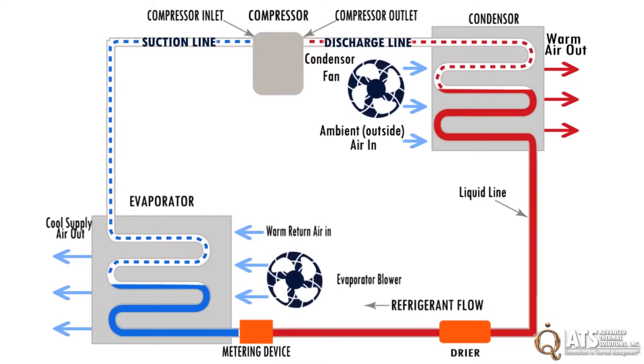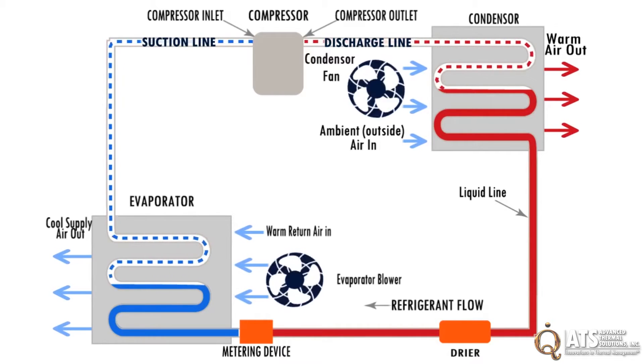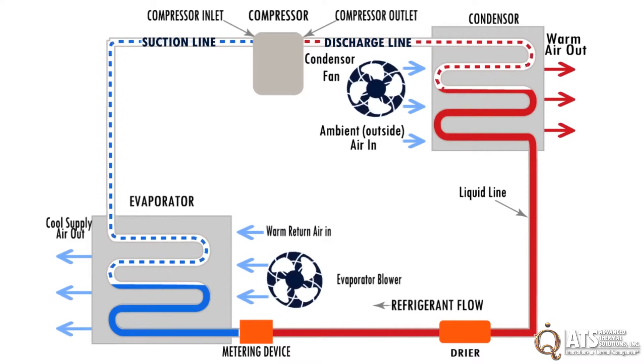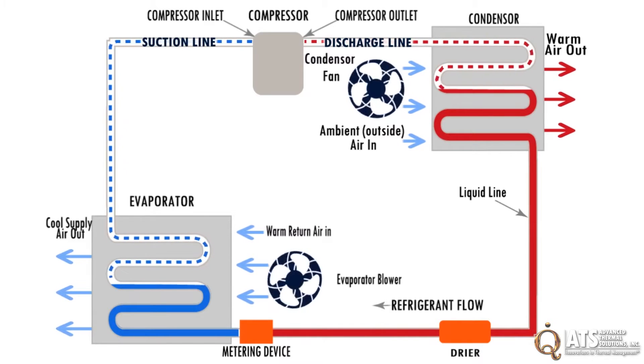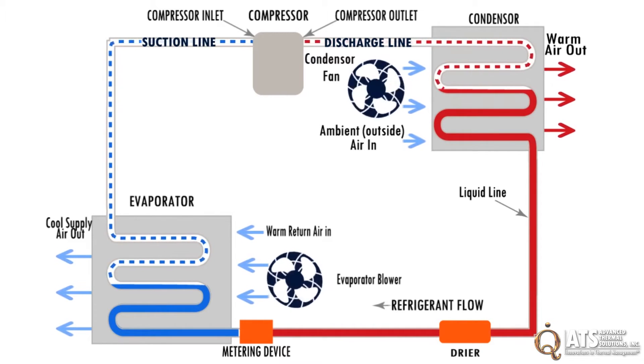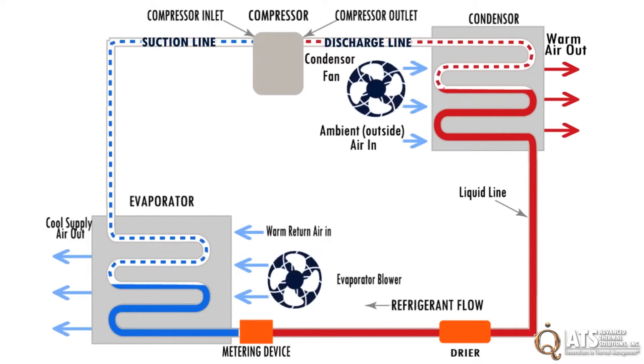The ATS recirculation chiller's refrigeration cycle shows red dashes where elevated-temperature, high-pressure refrigerant gas flows. Solid red shows the chiller's warm high-pressure refrigerant liquid. Solid blue shows the chiller's cold low-pressure refrigerant liquid, and the blue dashes show where the warm low-pressure refrigerant gas is.